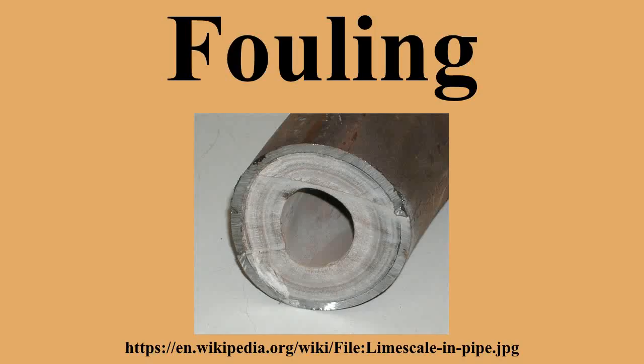The periodic variations are often interpreted as periodic removal of some of the deposit. Steam blanketing has been postulated to occur between the partially spalled deposits and the heat transfer surface. However, other reasons are possible, e.g., trapping of air inside the surface deposits during shutdowns or inaccuracy of temperature measurements during transients.